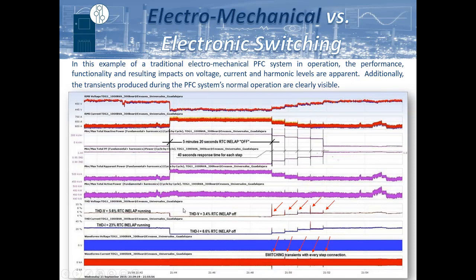But if the systems aren't designed properly, they can actually have a negative impact on harmonics. You can see here that with the system engaged, they're running at about 5.6 THD on their voltage, which is quite high. With the system off, it's a lower harmonics level, because oftentimes these systems aren't designed properly to account for the harmonic spectrum. If they don't have any reactors or inductors internal to them that are tuned specifically to the harmonic spectrum seen on that network, they can actually amplify those harmonics, which further aggravates the wear and tear on equipment.